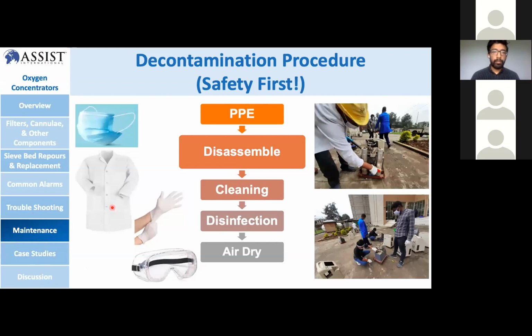Yeah, so the decontamination process. In this process, we start with personal protective equipment. We prepare all the personal protective equipment. That means masks, gowns, gloves, goggles if possible, so that we protect ourselves first. So we decontaminate all equipment because we consider all equipment contaminated. This decontamination process is usually cleaning, disinfection, and sterilization, but this last one, sterilization, we don't use, because the equipment that we use is non-immersible, as it is electrical and battery operated. We use non-immersion techniques because the equipment would be damaged, and we only do cleaning and disinfection.